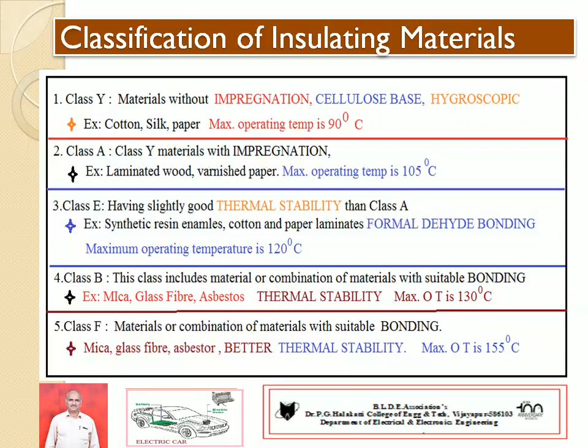Next class, class H insulation material. This class includes materials or combinations of materials such as silicone elastomer. Very important, the bonding substance used is silicone resins. Examples are built up mica and silicone resins. Maximum operating temperature of this class is 180 degrees centigrade. Last, the highest thermal capability of insulating material is class C. This also consists of materials with or without organic binder. Examples are mica, porcelain, glass, quartz and ceramics. Ceramics are generally referred to as having better thermal stability. Hence, this class operating temperature is above 180 degrees centigrade, or we can write 220 degrees centigrade.